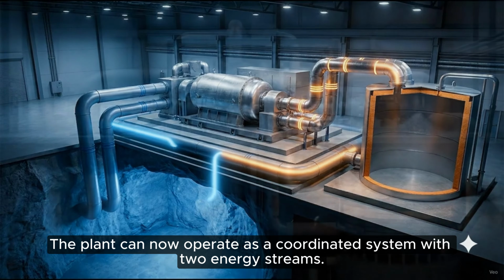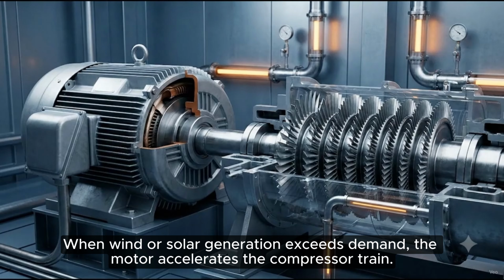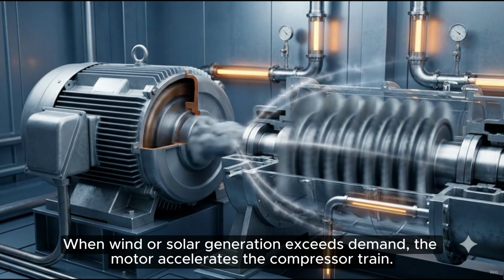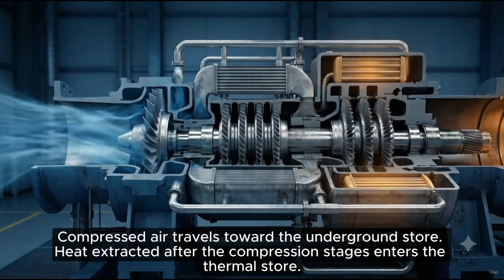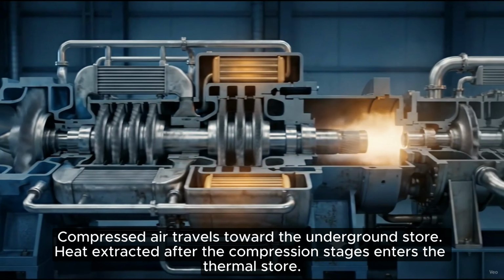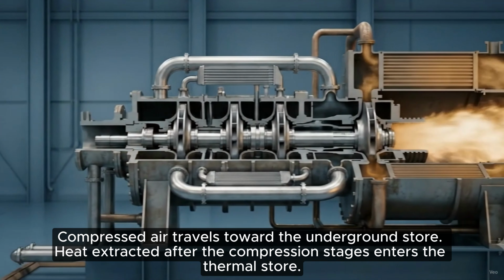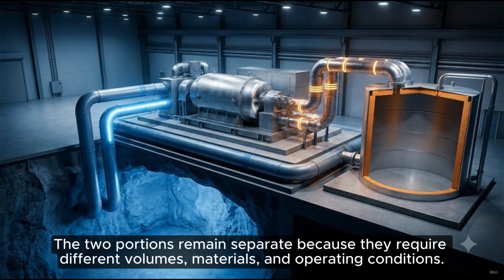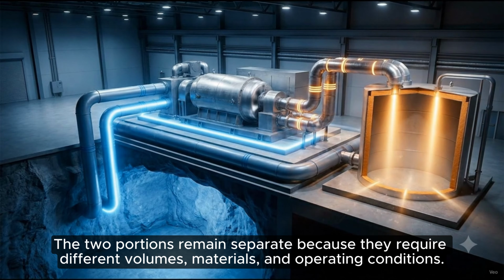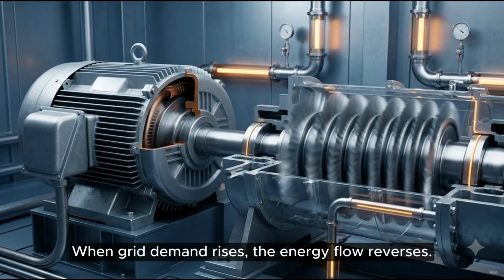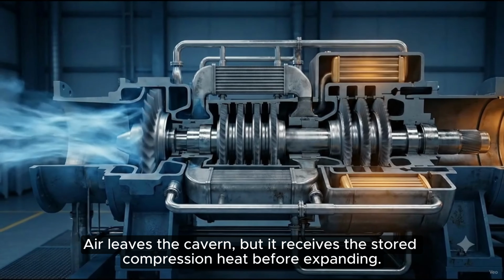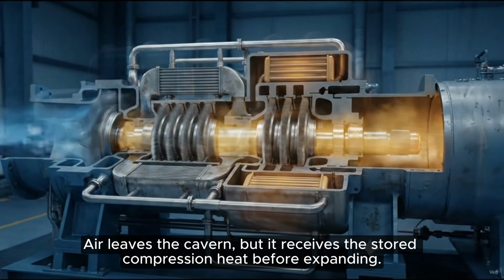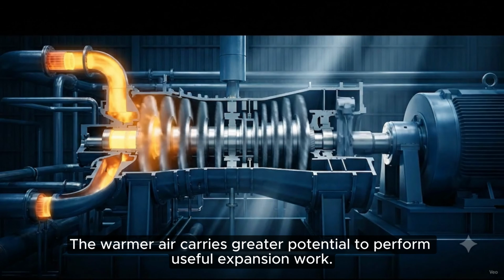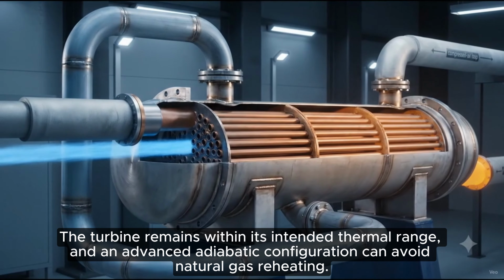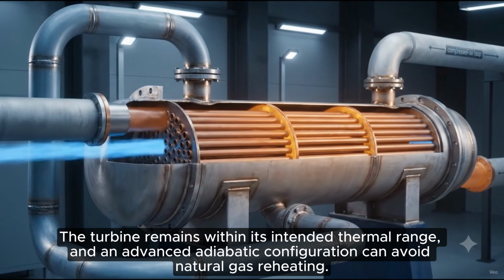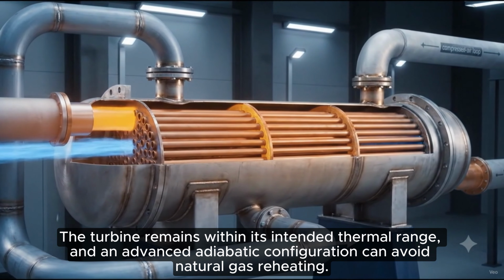The plant can now operate as a coordinated system with two energy streams. When wind or solar generation exceeds demand, the motor accelerates the compressor train. Compressed air travels toward the underground store. Heat extracted after the compression stages enters the thermal store. The two portions remain separate because they require different volumes, materials, and operating conditions. When grid demand rises, the energy flow reverses. Air leaves the cavern, but it receives the stored compression heat before expanding. The warmer air carries greater potential to perform useful expansion work. The turbine remains within its intended thermal range, and an advanced adiabatic configuration can avoid natural gas reheating.